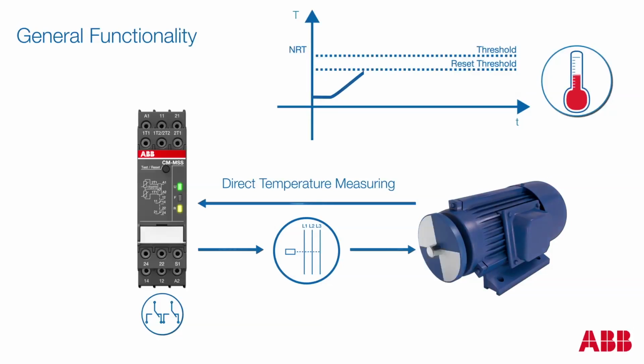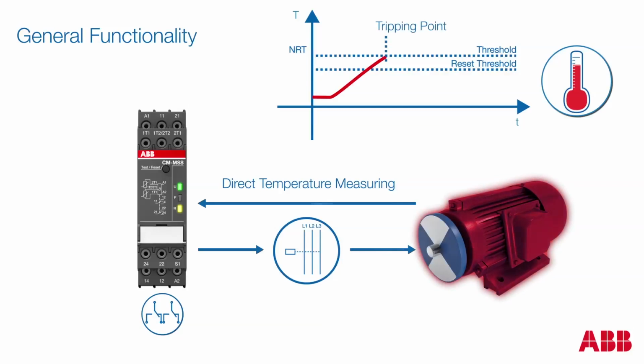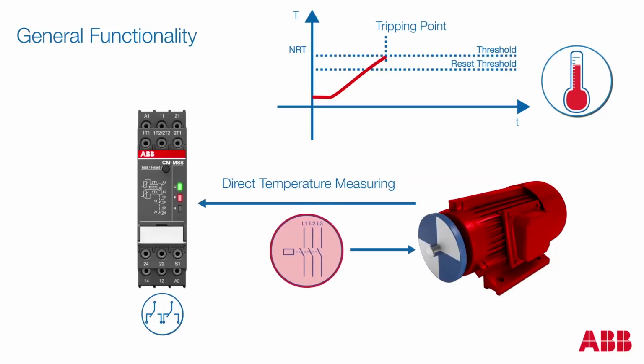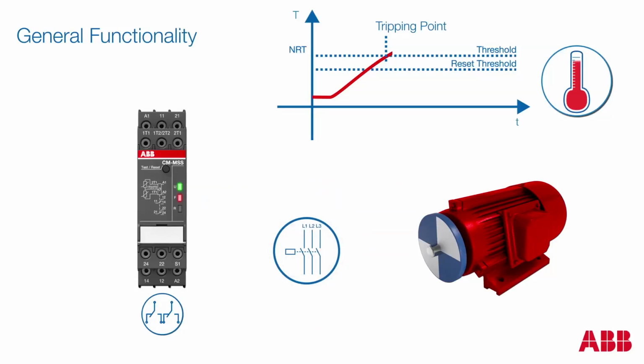The thermistor motor protection relay measures the resistance of the PTC sensors, which reflects the internal motor temperature permanently. If the temperature in the motor windings rises excessively and reaches the nominal response temperature (NRT), the thermistor motor protection relay detects the situation and the output relay switches off. By doing so, the motor contactor gets triggered and switches off the motor.